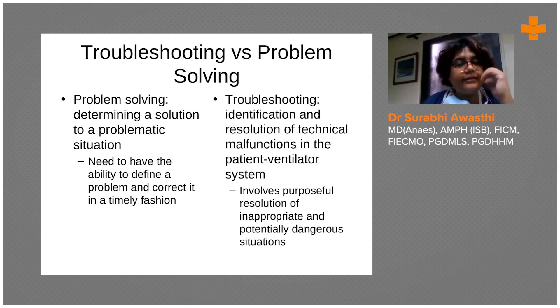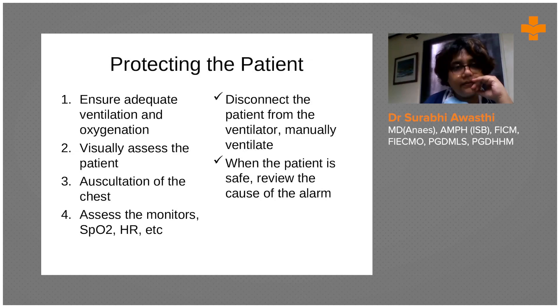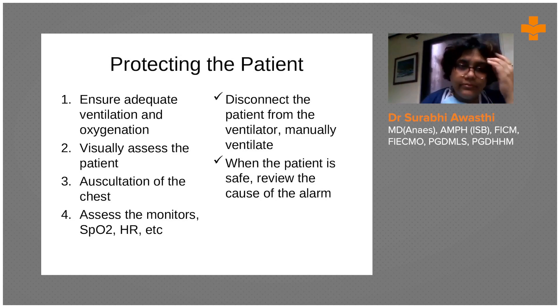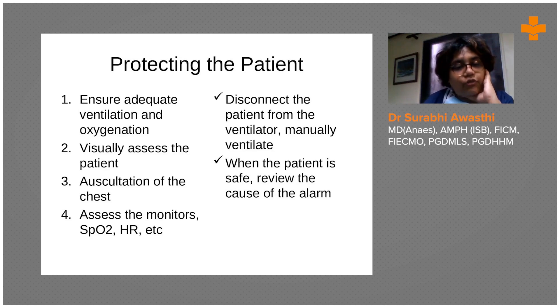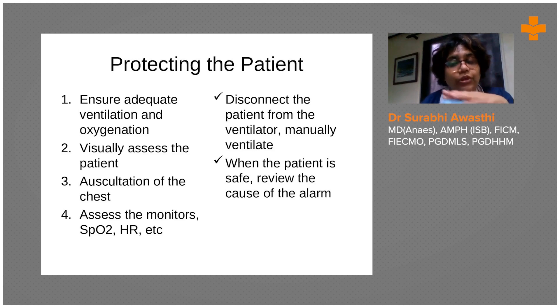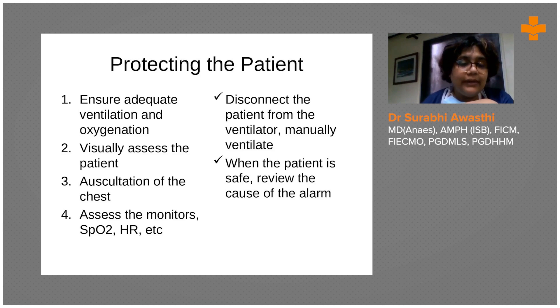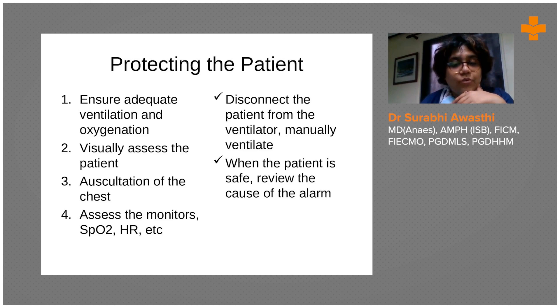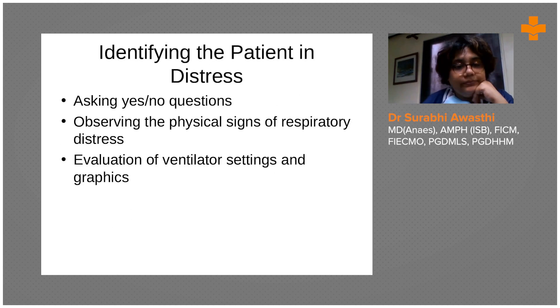When discussing problem solving and troubleshooting, before you do anything for the patient or when ventilator alarms occur, you need to first protect your patient. Ensure oxygenation first - visually assess the patient and auscultate his chest, assess the monitors, and after doing all that, disconnect the patient from the ventilator and manually ventilate him, either with the Bain circuit or with the Ambu bag. Once the patient is okay and safe, then you can go back to the ventilator and review the alarms.